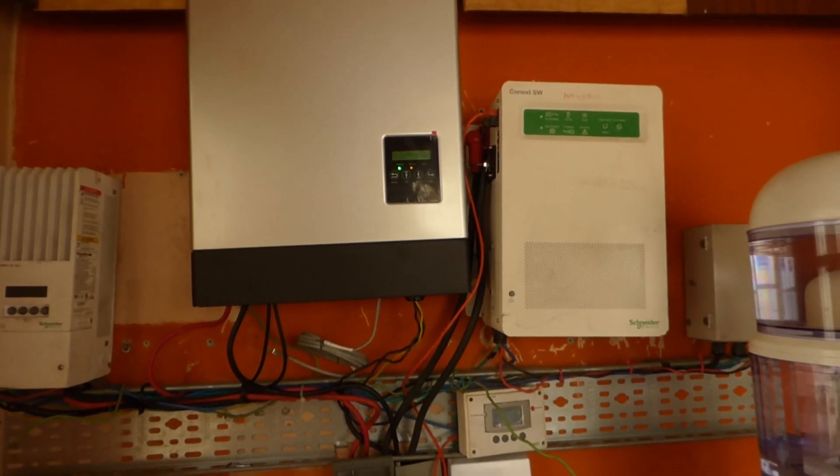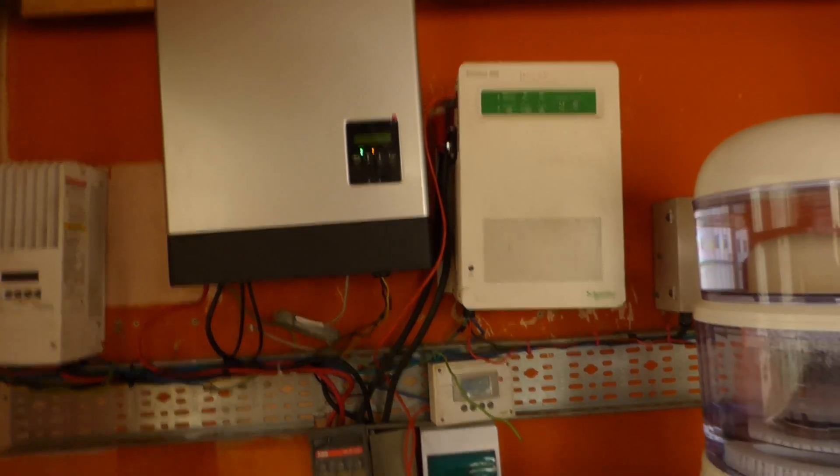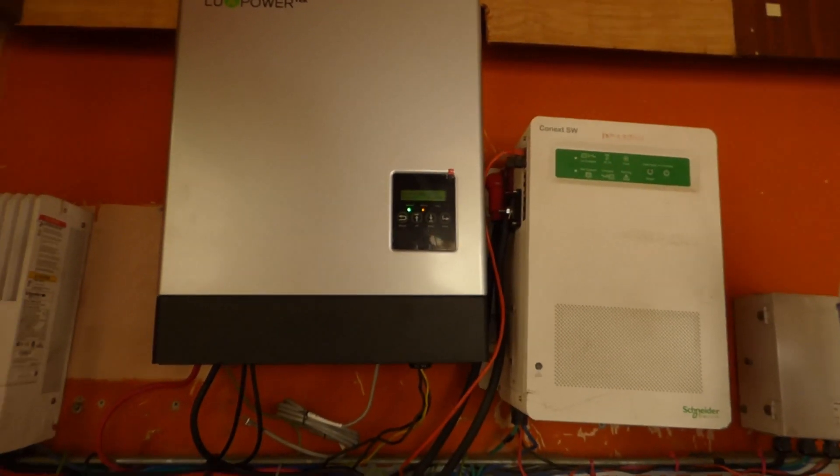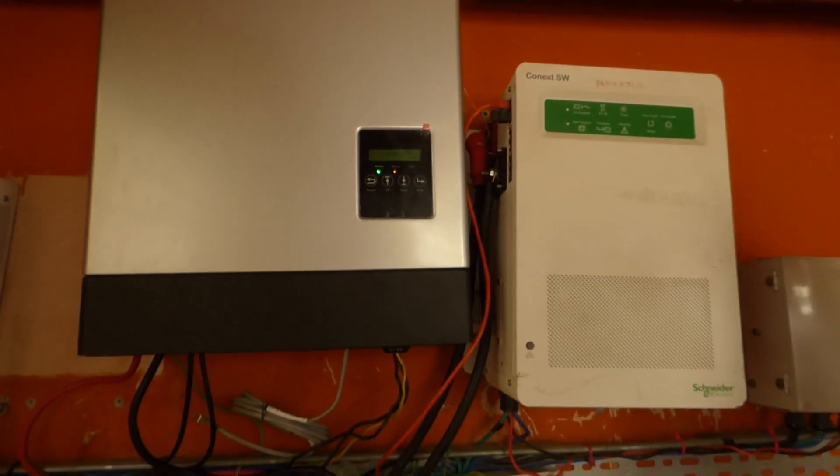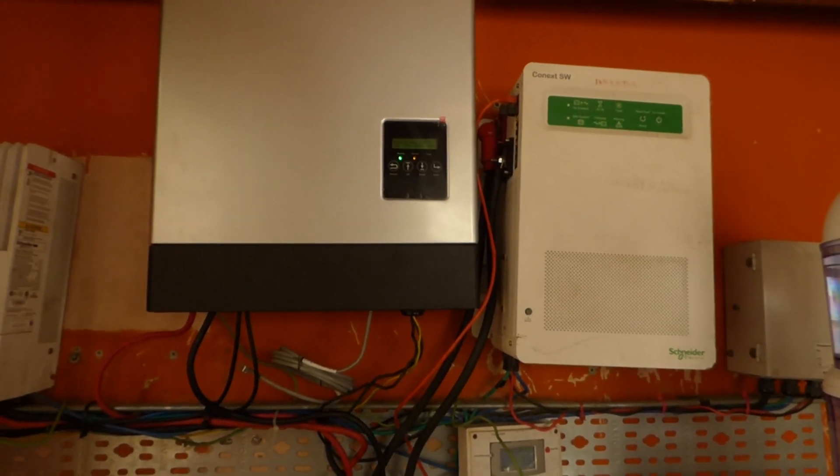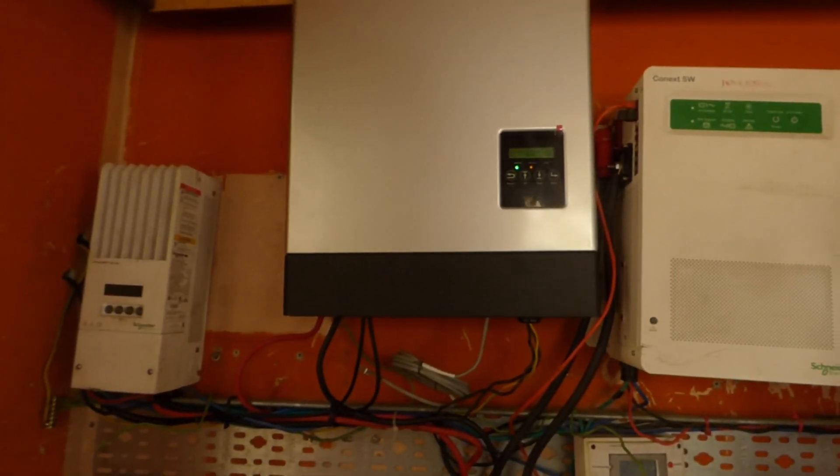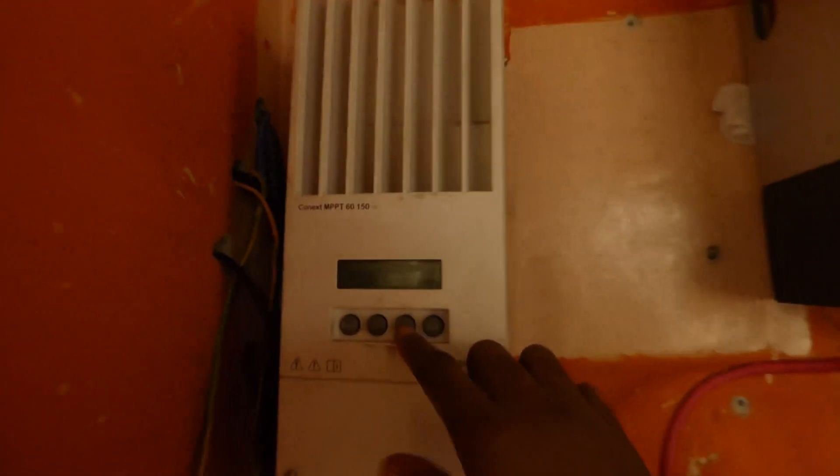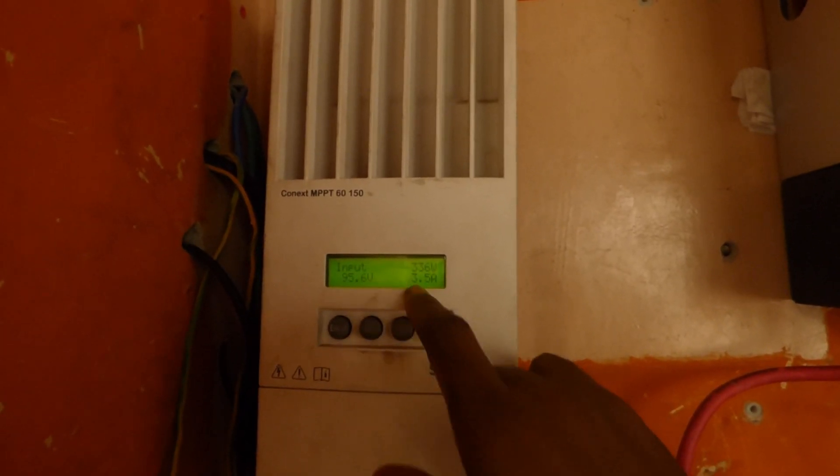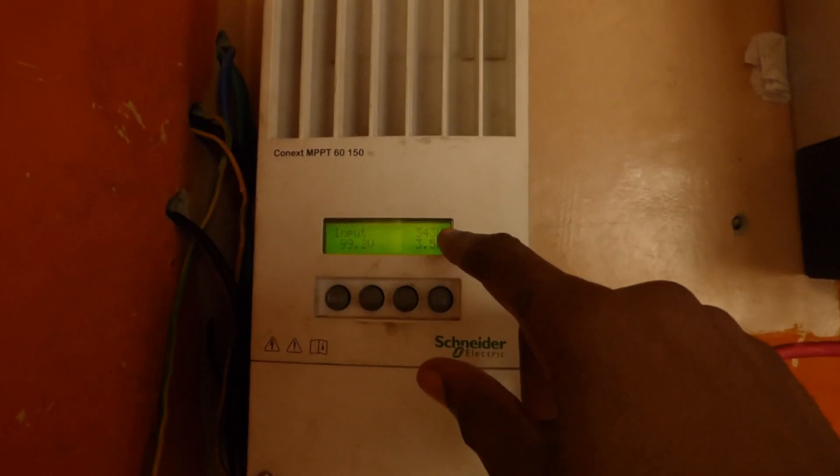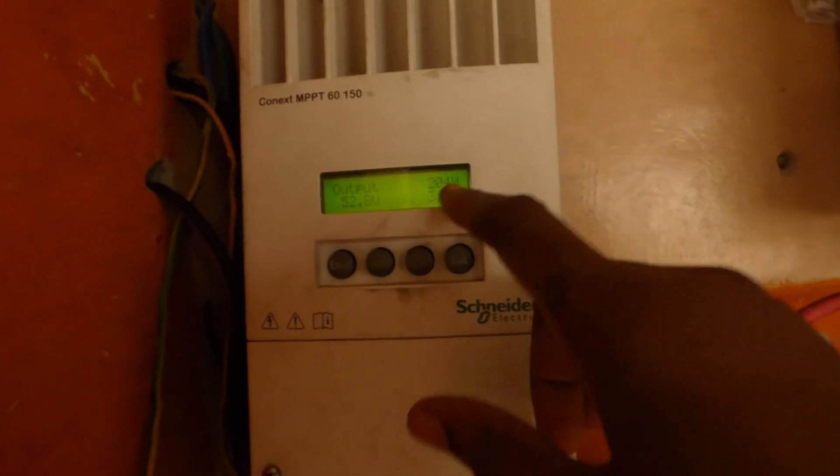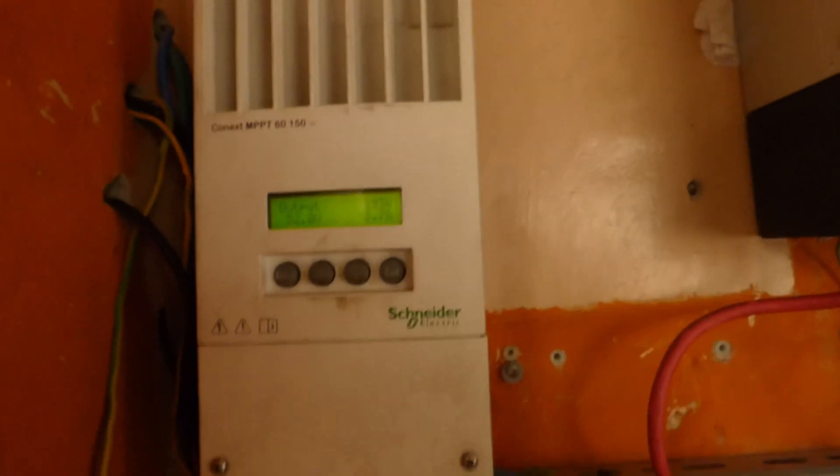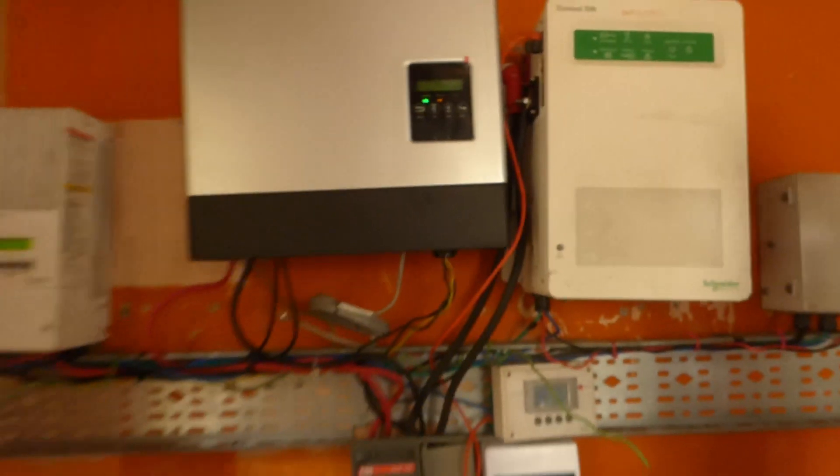One other thing also is we're running - our panels are producing about 130 to 140 volts, and times 80 percent we're seeing about 104, 105, 106, 107. So that's what the system is working off of - not the short circuit voltage or open circuit voltage. It's working off loaded voltage. On our old charge controllers, even loaded, that's the voltage we saw, but this charge controller shows you two bits of information. It shows you input, which is what's coming to your batteries - sorry, it shows output is what's coming to your batteries. Input shows you your voltage 99.2 and then 3.5 amps, and then it steps that down to 52.8 volts and then 3.7 amps.